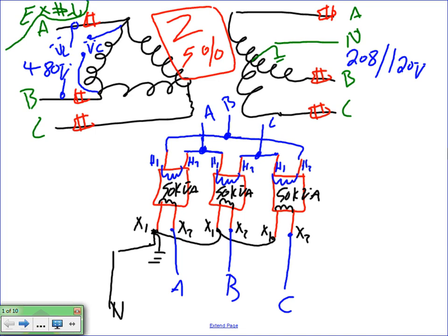We're looking at, first of all, physical mechanical transformers. I have one big barrel, and a second and a third. Each one of them is a 50 kVA single phase transformer. And I know you guys have done it with me and with Gary. Then we bank them together to make a three-phase system.